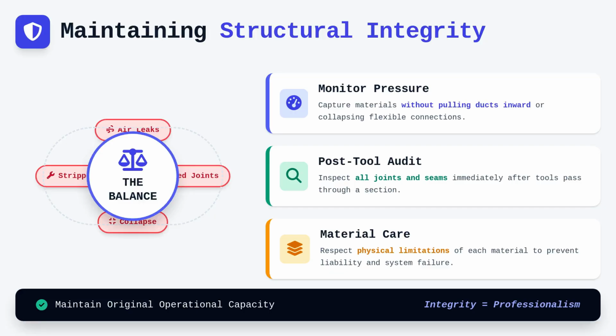You need to verify that your negative air machines are providing sufficient suction to capture dislodged materials without pulling the ducting inward or collapsing flexible connections. This balance is precarious, but it is essential for maintaining the operational capacity of the ventilation system long after you leave the site. Always inspect the joints and seams after your tools have passed through a section to ensure no seals have been stripped or joints have been separated.